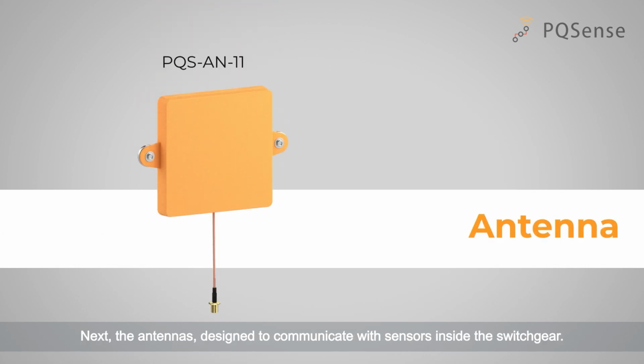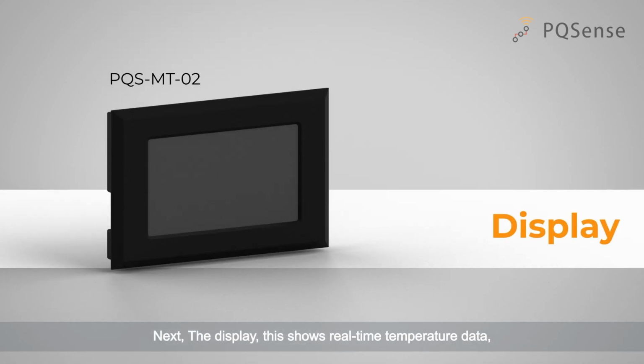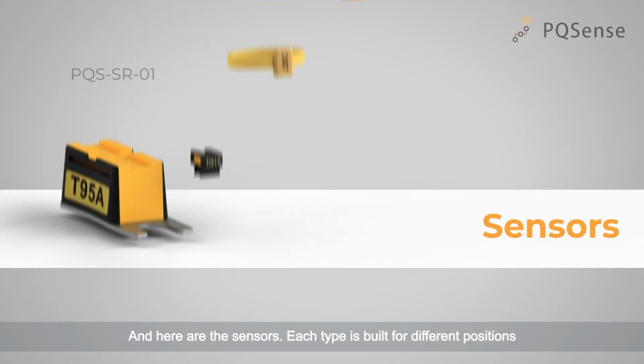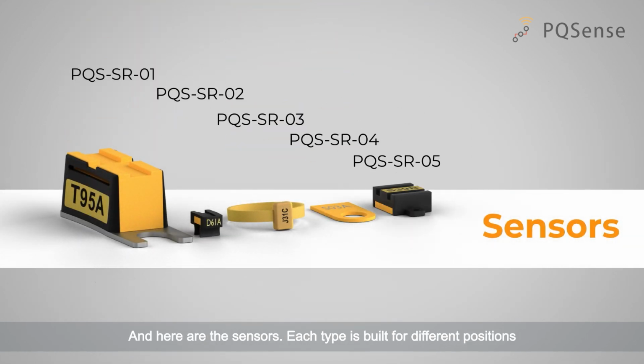Next, the antennas, designed to communicate with sensors inside the switchgear. Next, the display. This shows real-time temperature data, helping you identify hotspots at a glance. And here are the sensors. Each type is built for different positions: cable joints, contact points, or bus bars.